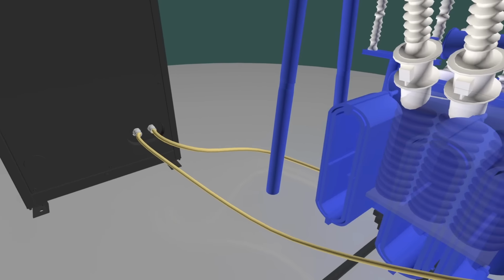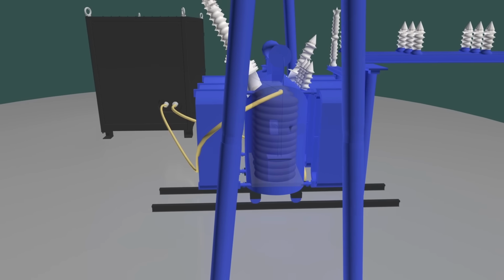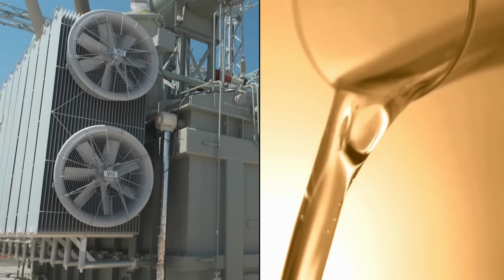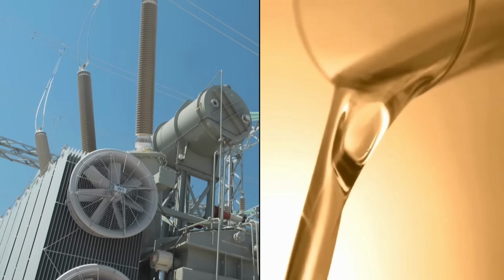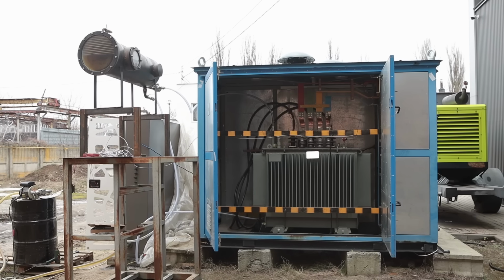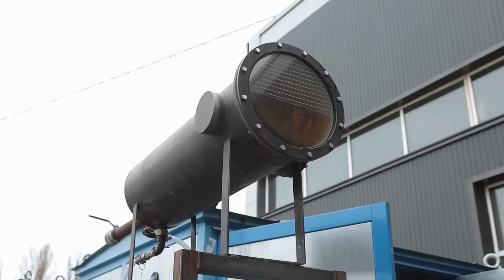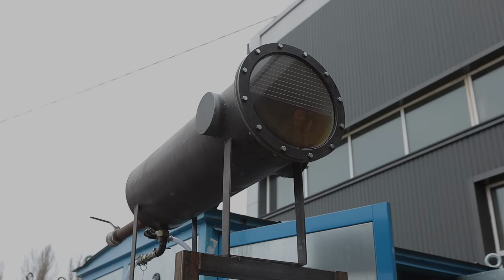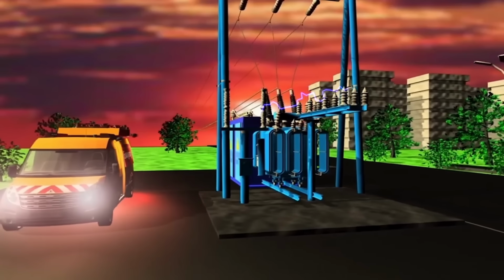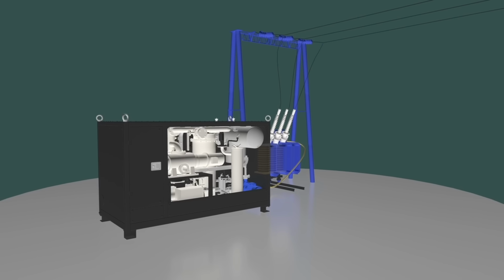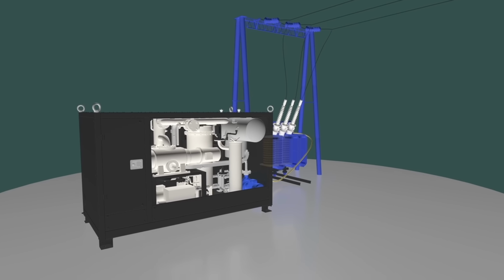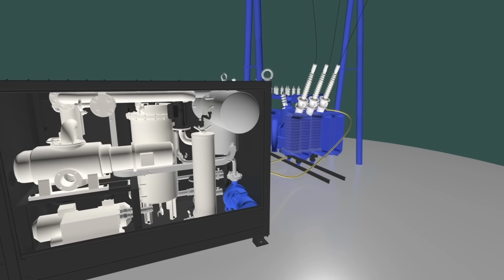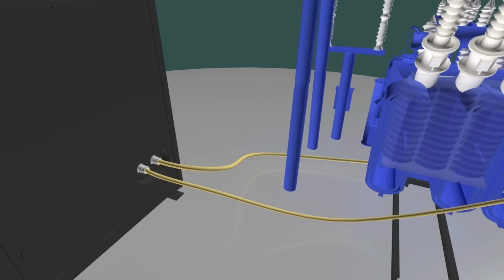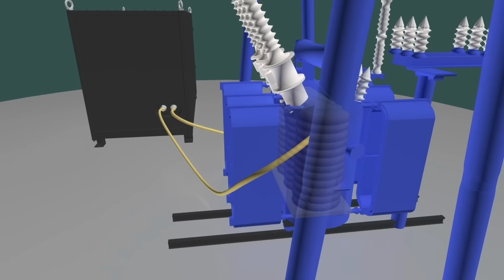Transformer drying with the use of CMMRM hot oil sprayer begins with almost complete draining of oil from the transformer tank. GlobeCore recommends that not more than 10% of the initial volume be allowed to remain in the tank. Next, the hot oil sprayer is installed above the transformer's active part in combination with a manifold.